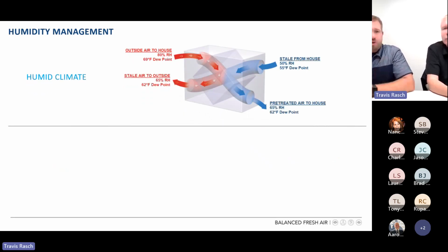Similar to temperature, in a humid climate we've got a higher dew point outside. We've either used a dehumidifier or air conditioning to maintain our relative humidity and dew point inside, so we're going wet to dry. We've got wet, humid air coming in, in this case to the ERV, and we take that drier air from the inside, pass it across that core, and that moisture vapor exchanges like we showed earlier, carrying some of that humidity back to the outside.